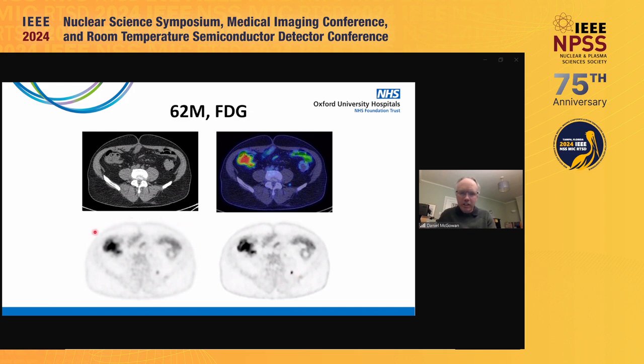But we thought the skin uptake on the BSREM image looked a bit hotter. So we thought, has something gone wrong with attenuation correction? Because obviously for a non-attenuation corrected image, you get this hot skin effect. Or has something happened with our reconstruction?